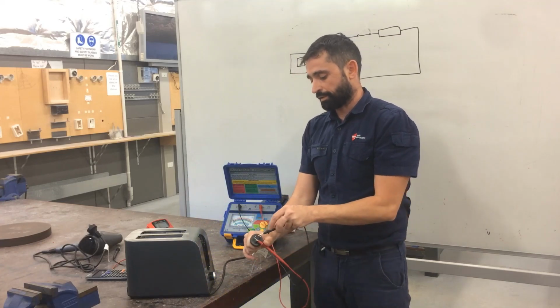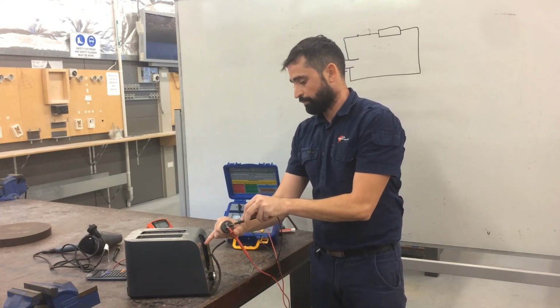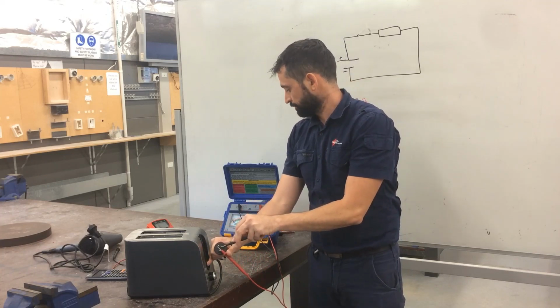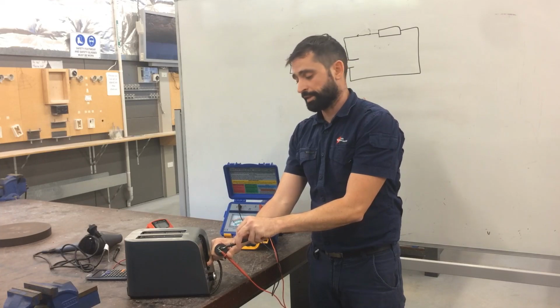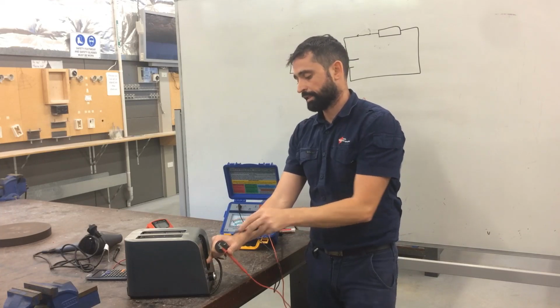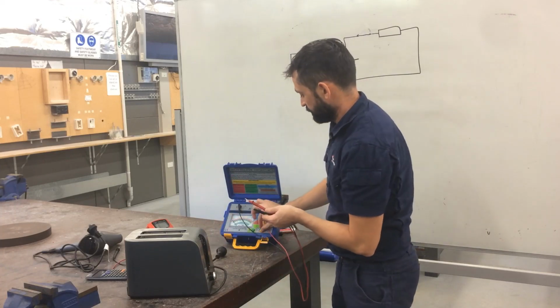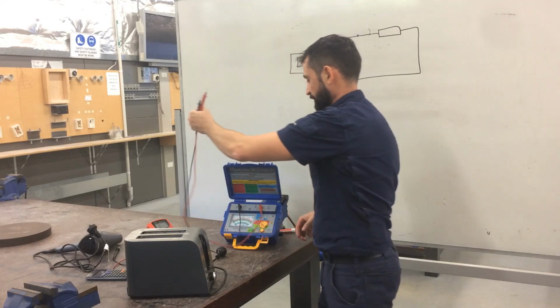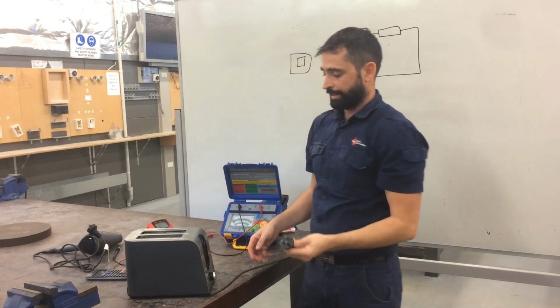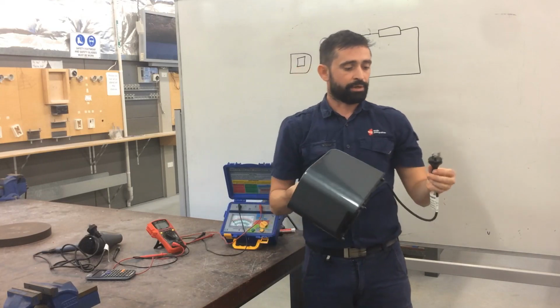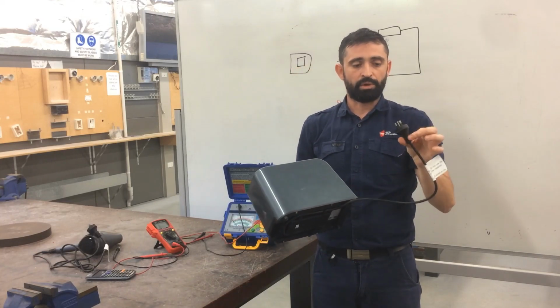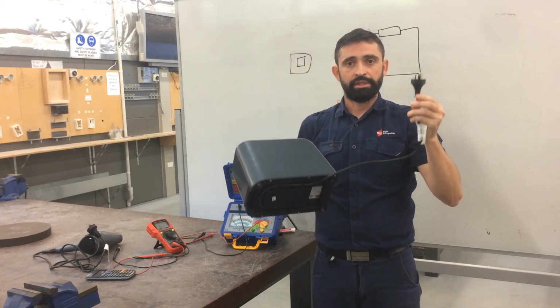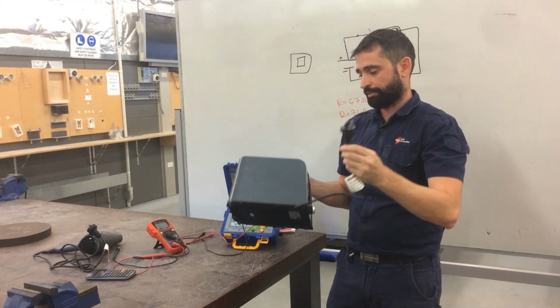However, we're going to measure down to earth. So we're going to put it against the earth, and don't forget to turn the toaster on. Cool. So it's on infinity ohms. That's what we want. Excellent. Don't forget to turn your insulation resistance tester off. Cool. Now the final test that we do is the polarity test. However, we can't do a polarity test with a molded plug. This comes direct from the manufacturer. So we can't do that test, so that's fine.